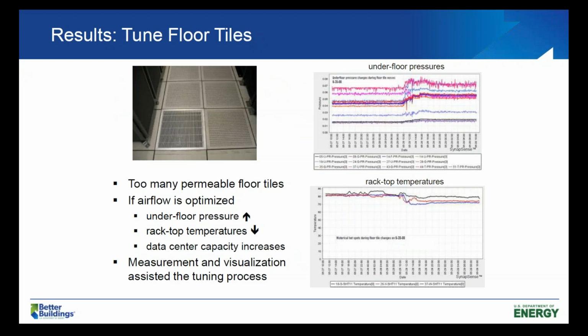All right, so too much open tile area is at least as much of a problem as too little. It'll result in very low underfloor pressures, which will make it difficult for adequate airflow to reach the tops of the racks. So whenever you see wide open tiles, that's an indication that things are probably out of balance. One can measure this either with temperatures, as is shown here on the lower right of this slide, or in a more sophisticated way with pressures. But the bottom line is the IT equipment needs to get an adequate supply of cooling air. Next slide, please.